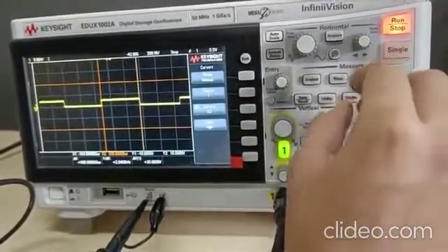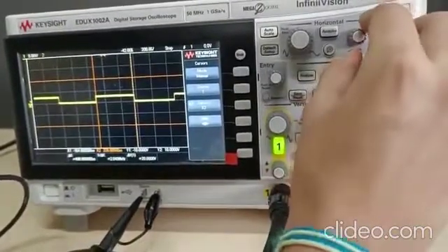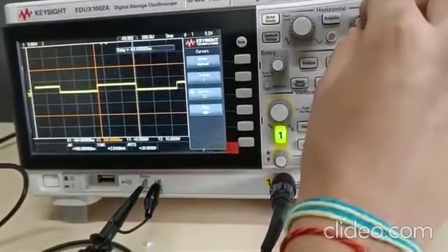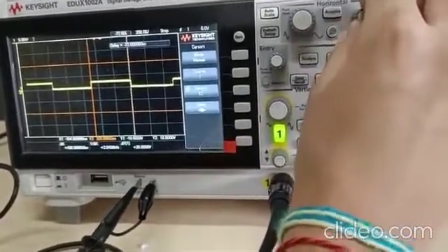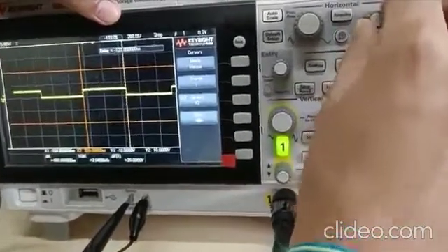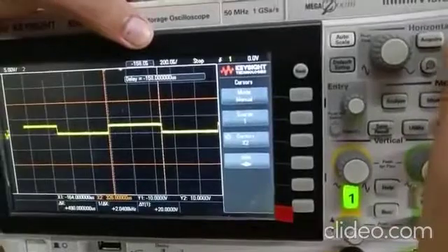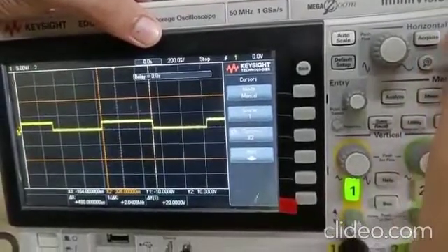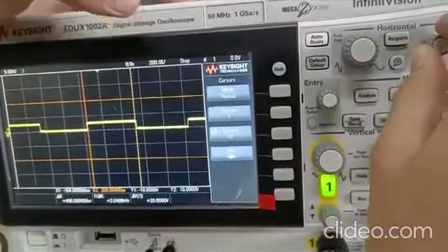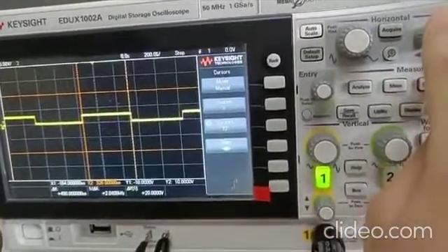To align the waveform with Y axis, we can select the X position knob and we can see the delay. When delay becomes 0, this means the waveform is perfectly aligned with Y axis.